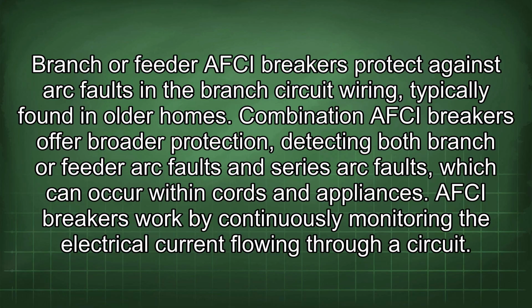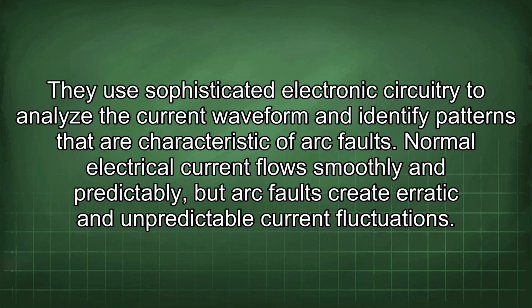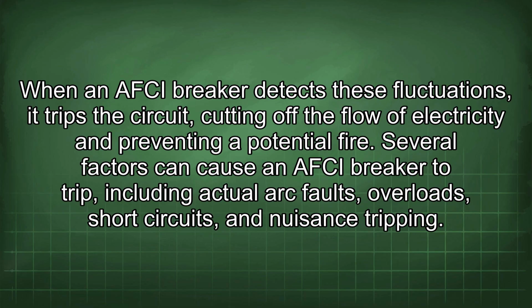AFCI breakers work by continuously monitoring the electrical current flowing through a circuit. They use sophisticated electronic circuitry to analyze the current waveform and identify patterns that are characteristic of arc faults. Normal electrical current flows smoothly and predictably, but arc faults create erratic and unpredictable current fluctuations. When an AFCI breaker detects these fluctuations, it trips the circuit, cutting off the flow of electricity and preventing a potential fire.